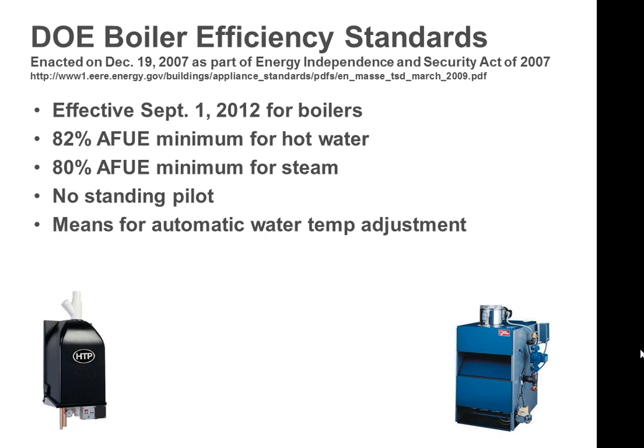Along with that change was the elimination of standing pilots, which most of these systems have already done anyway. Interestingly, there is now a requirement that, from the boiler standpoint, you have a way to automatically adjust the water temperature set point. For most of us and most of our systems, that's going to mean outdoor air reset control that you'll have to do by law on these systems. All that is going to play into radiant heating as we go along. In about 2017 or so, you're going to see 90% as the minimum boiler efficiency. But that's still 5 years away, so you still have time on that one. Right now, 82% is the minimum for hot water.